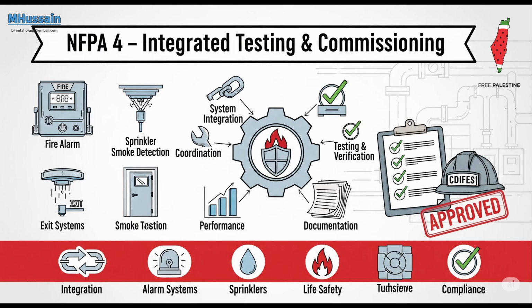Did it pass? Did it fail? How did it perform? A complete history of the performance. Exactly. And if any test result doesn't comply with the design intent, if something failed, a detailed description of that fault has to be recorded in an issues log. And for every single non-compliance found, a separate corrective action report must be prepared. What does that entail? It provides specific details of what went wrong, and importantly, what was done to fix it, the remediation. This isn't just bureaucratic busy work. It ensures there's a clear path to resolution, assigns accountability, and prevents problems from just getting ignored or forgotten. Creates a clear record of problems found and problems solved.